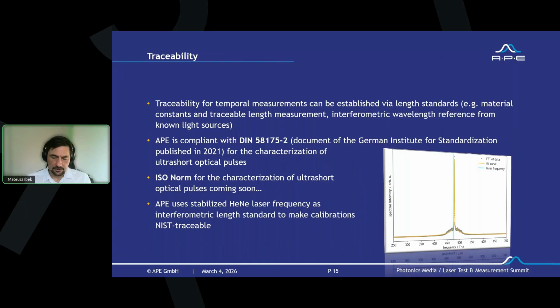So how about traceability? How do we know that these devices measure correctly? Traceability for temporal measurements can be established via length standards, for example material constants and traceable length measurement, like interferometric wavelength references from known light sources. We at APE are compliant with the German industrial norm DIN 58175-2. This is from the German Institute for Standardization, and it published a document in 2021 for the characterization of ultrashort laser pulses. We are also working actively on the ISO norm, which is coming soon. This will be the international norm for the same purpose, for the characterization of ultrashort laser pulses.